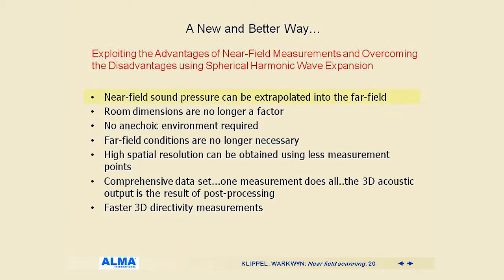This is what we get. Near field sound pressure can be extrapolated into the far field now. It's no longer a problem. Room dimensions are no longer a factor. No anechoic environment required. Far field conditions are no longer necessary.